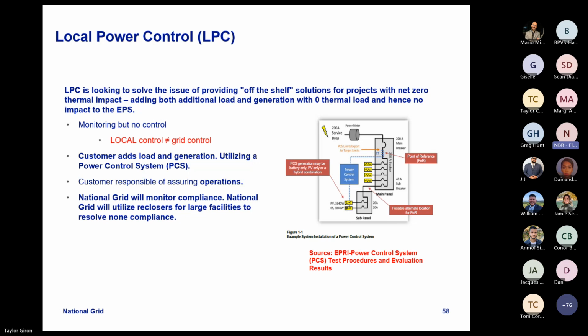What we're really looking for are off-the-shelf type solutions. There are a number of listed controller and inverter combinations that are found to work together, so they're UL certified. Those tend to be at the 150 kW or below level. We're trying to explore those off-the-shelf systems so that in the future it can enable a more expedient interconnection process—if you're using a listed system in a certain facility, we may be able to find opportunity to expedite the connection process going forward.